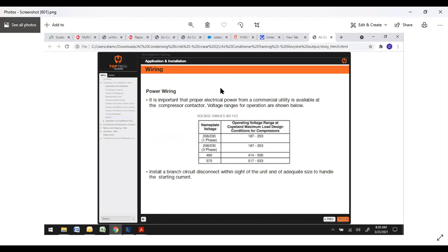Okay, your power wiring. It is important that proper electrical power from your commercial utility is available at the compressor contactor. Voltage range, for 208/230 single phase, you have to have a minimum of 187 and a maximum of 253. If you're closer to 187, chances are your compressor is not going to start. Usually you're going to be in the 235, 246 range.